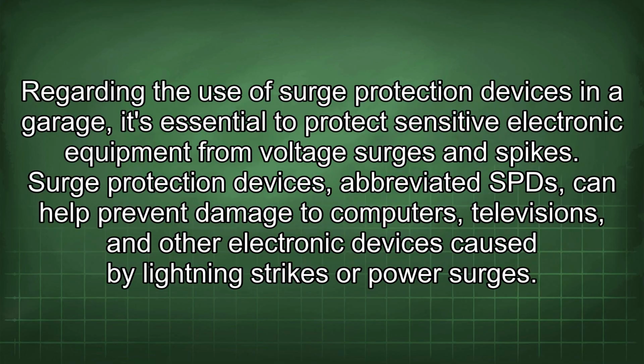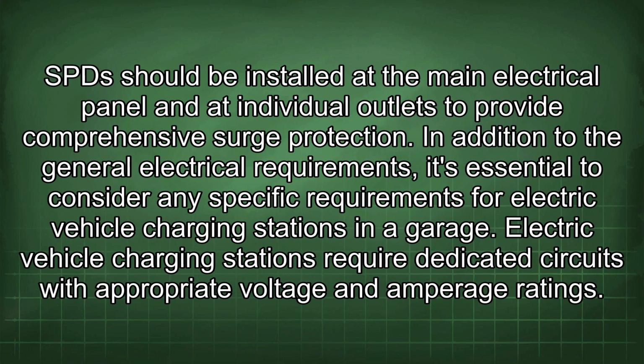garage. Regarding the use of surge protection devices in a garage, it's essential to protect sensitive electronic equipment from voltage surges and spikes. Surge protection devices, abbreviated SPD, can help prevent damage to computers, televisions, and other electronic devices caused by lightning strikes or power surges. SPD should be installed at the main electrical panel and at individual outlets to provide comprehensive surge protection.